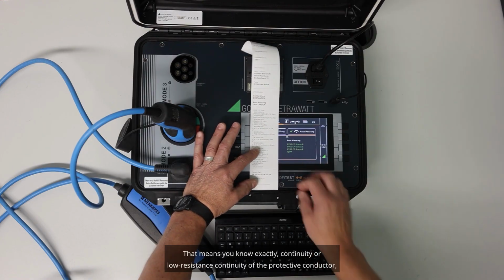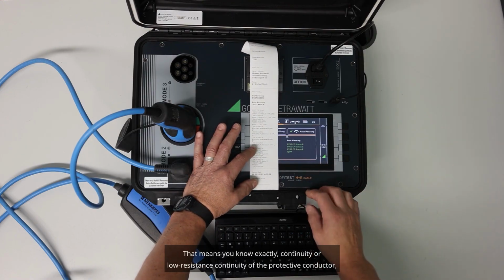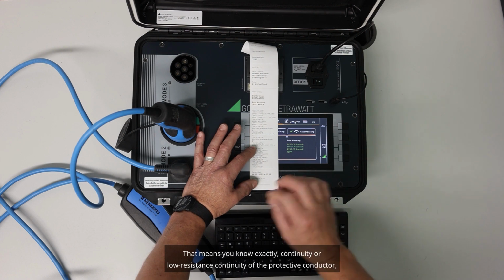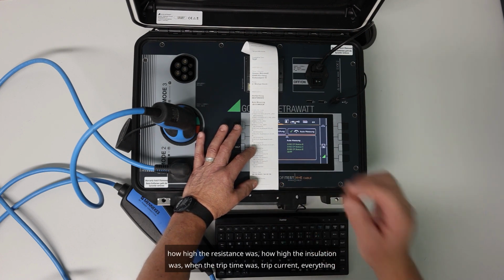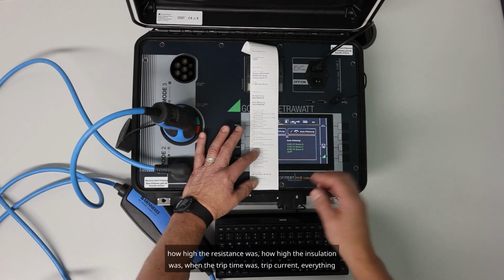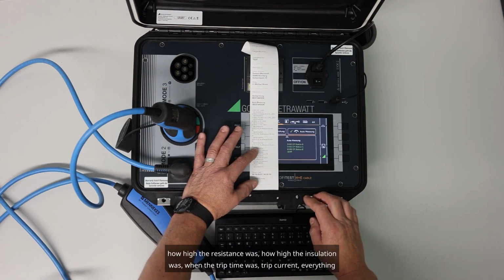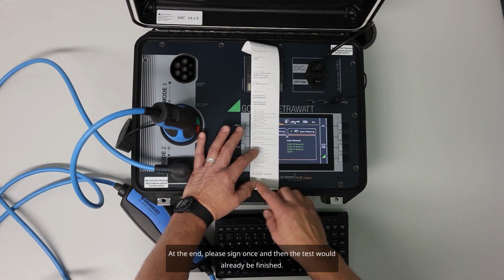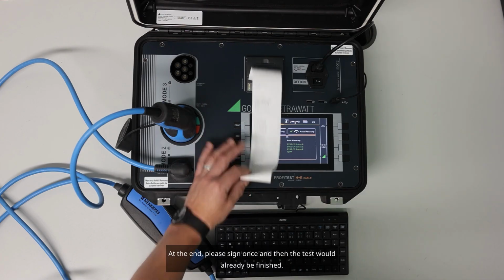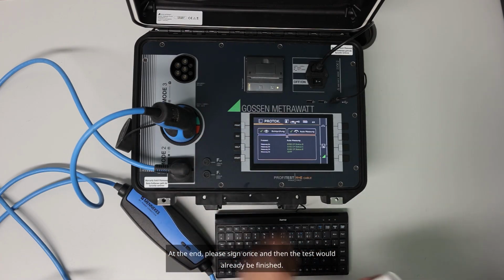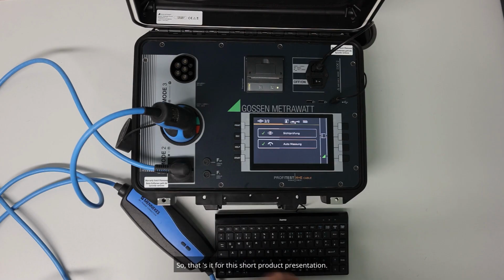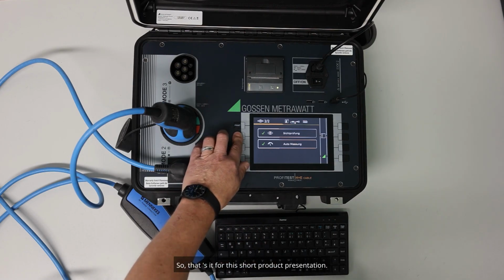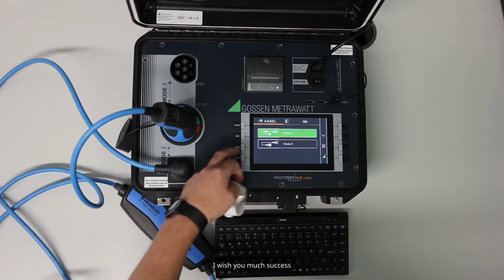That means you know exactly continuity or low resistance continuity of the protective conductor, how high the resistance was, how high the insulation was, when the trip time was, trip current, everything is documented. At the end, please sign once, and then the test would already be finished. So that's it for this short product presentation. I wish you much success with the testing.